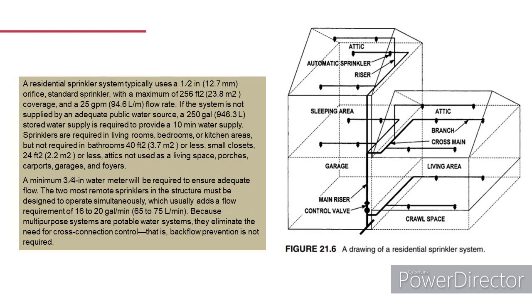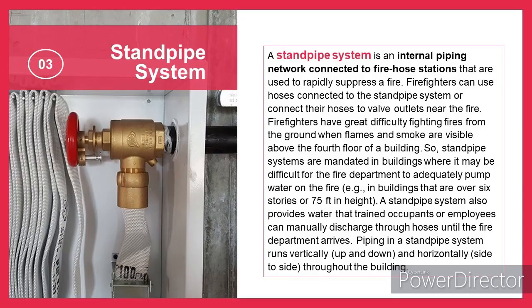The two most remote sprinklers in the structure must be designed to operate simultaneously, which usually adds a flow requirement of 16 to 20 gal/min, 65 to 75 L/min. Because multi-purpose systems are potable water systems, they eliminate the need for cross-connection control, that is, backflow prevention is not required. Now we are bound to tackle the third system, the standpipe system.